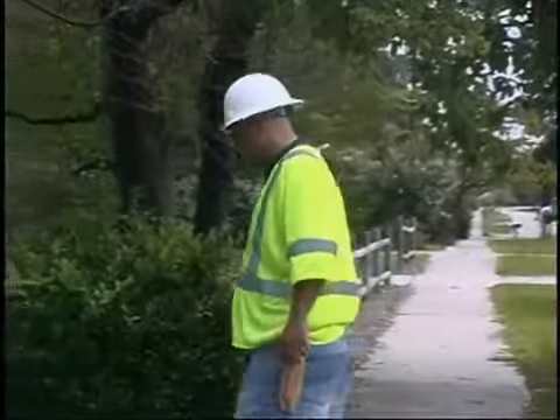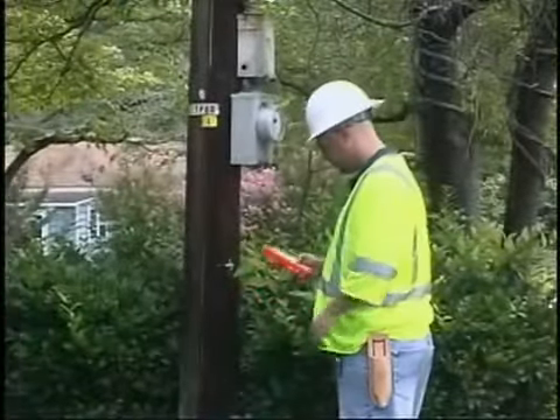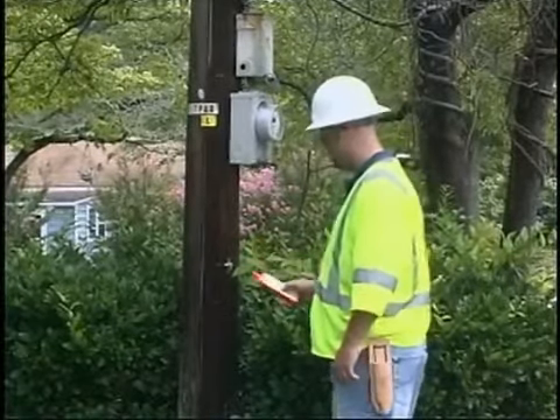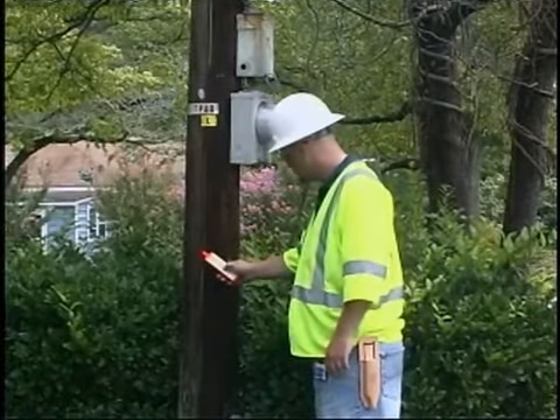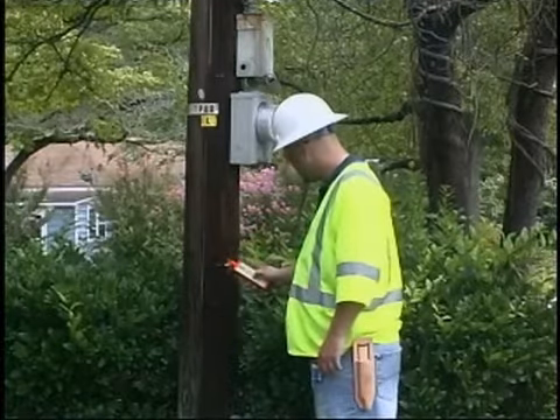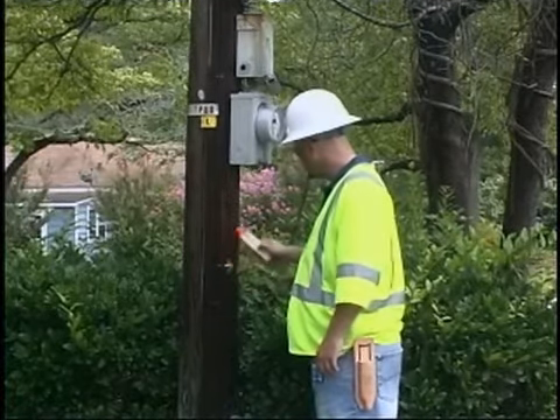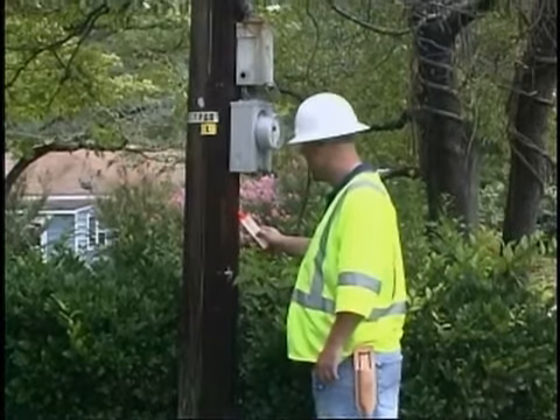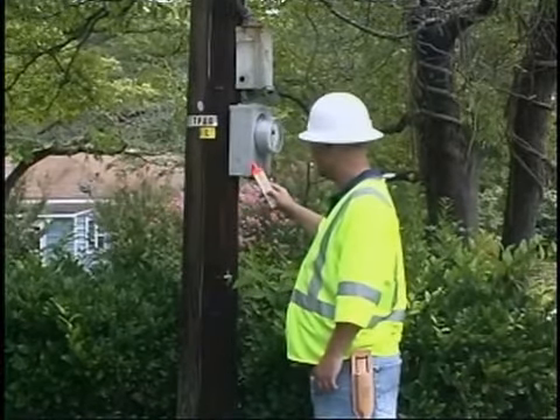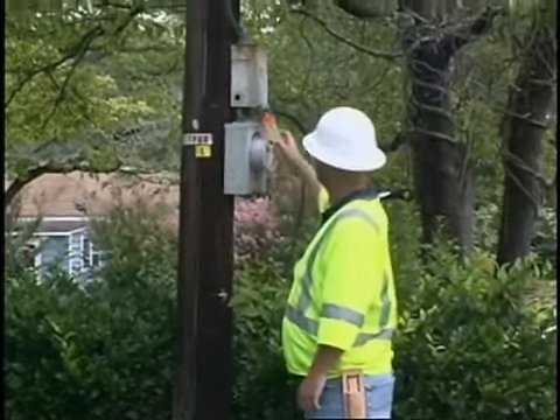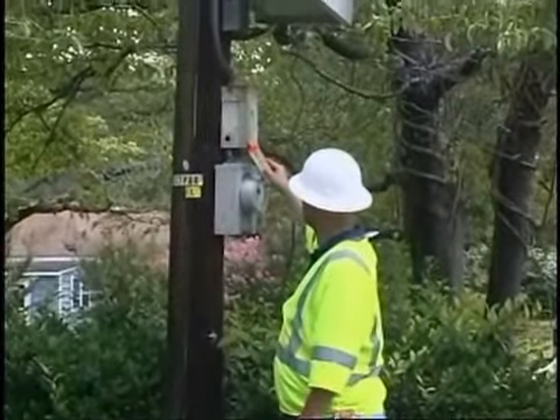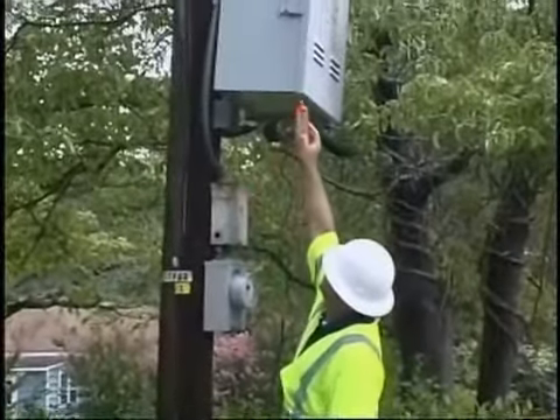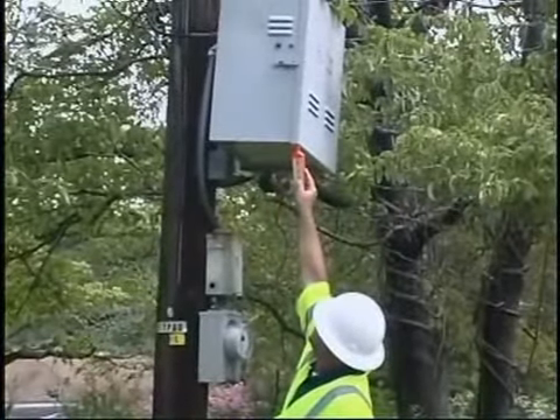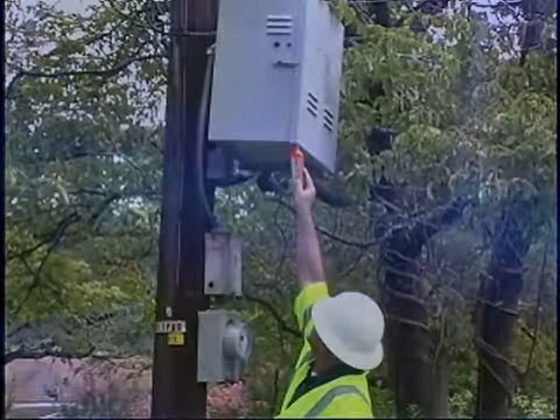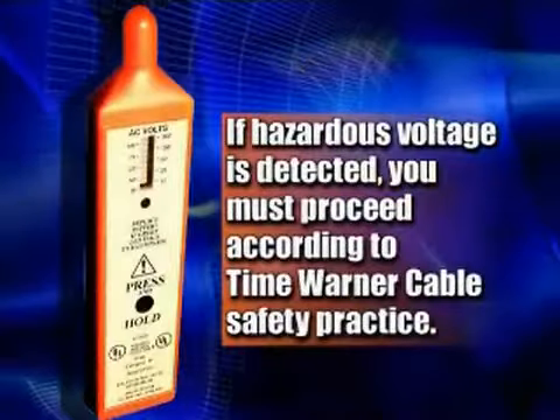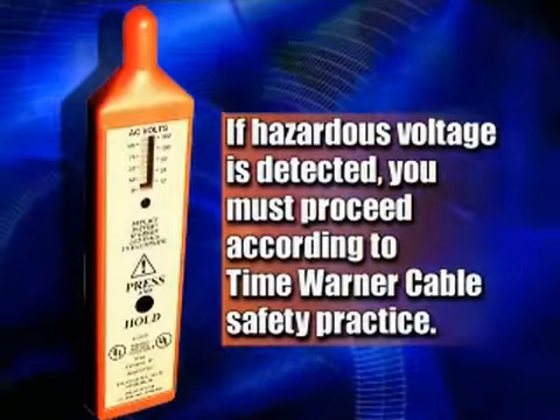To begin testing with the FVD, turn it on a few feet away from the suspected source. When all of the bar graph steps deactivate and the LED illuminates, point the probe toward the suspected source and slowly move toward it. Remember that any time the audible alarm sounds, it means that the source is greater than 50 volts. Continue toward the suspected source until the alarm sounds or the probe touches the source. If no alarm has sounded by the time the probe touches the source, you know the source is less than 50 volts. If hazardous voltage is detected, you must proceed according to Time Warner Cable's safety practice.